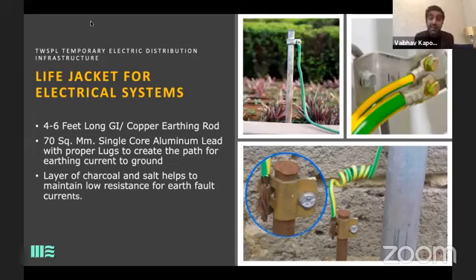The wiring size depends on the load of the genset. So if you're using a 62.5 kVA, which is giving you 30 kilowatts of power in a normal case in Bombay or maybe in Delhi, your neutral is always half. Neutral is half, meaning that the 3 phase wires are according to 30 kilowatts, but your neutral can be half, which is 15 kilowatts. So the same wiring size you require for earthing also. If I am using a 70 square mm, my 70 square mm wire can take up to a load of 40 kilowatts or 50 kilowatts for the earthing.